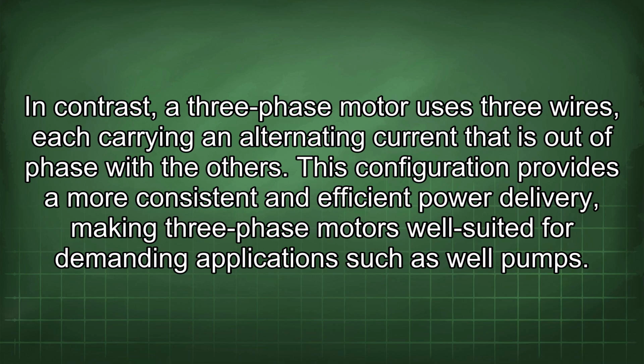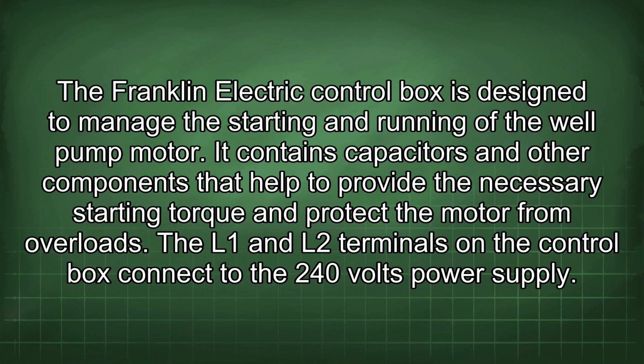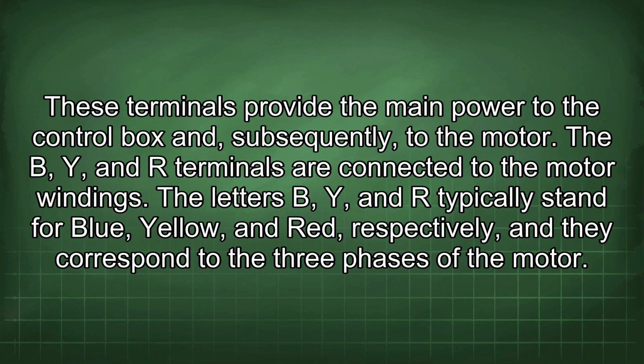The Franklin Electric control box is designed to manage the starting and running of the well pump motor. It contains capacitors and other components that help to provide the necessary starting torque and protect the motor from overloads. The L1 and L2 terminals on the control box connect to the 240 volts power supply. These terminals provide the main power to the control box and, subsequently, to the motor.